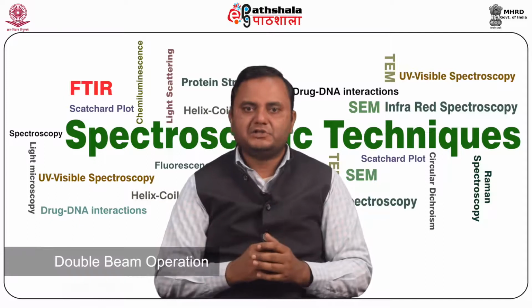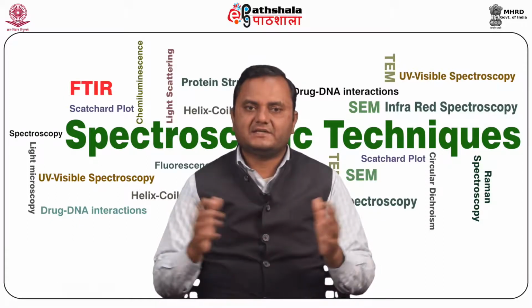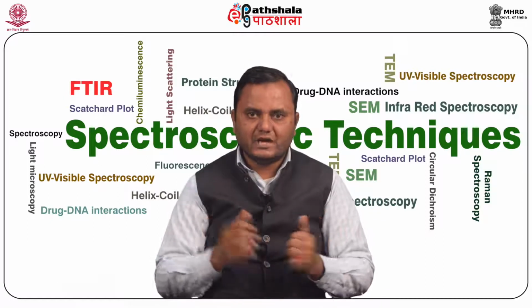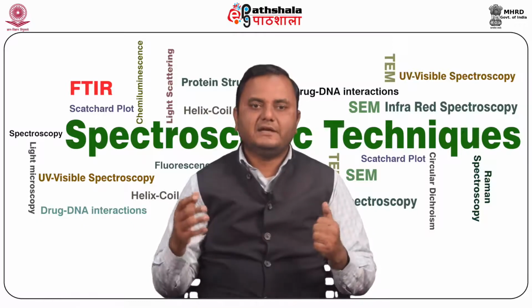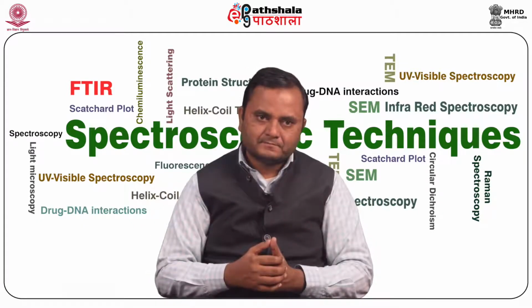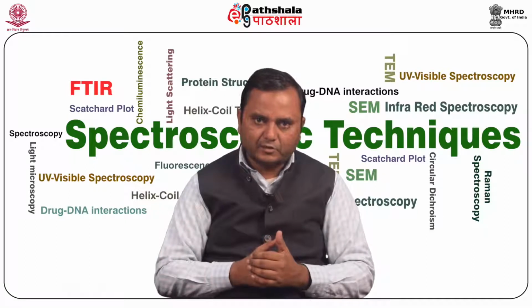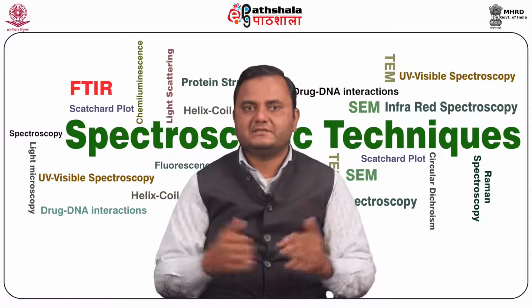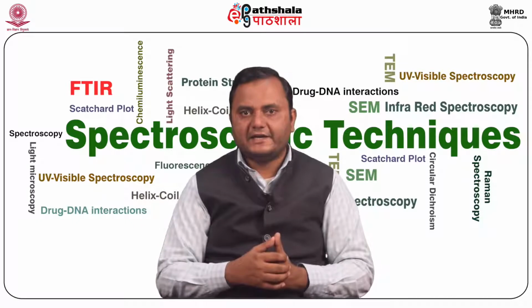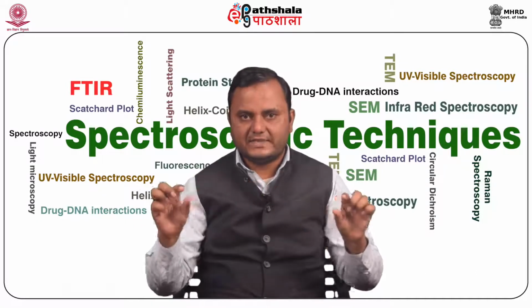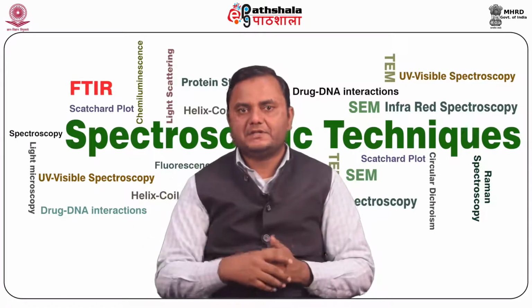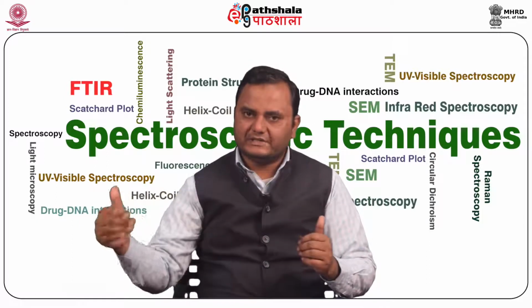In double-beam operation, the beam splitter separates the incident beam into two halves, half going to the sample and half to the reference. The sample absorbs light according to its chemical properties, and the detector collects the radiation that passes through the sample, and double-beam operation compares the energy going through the reference.